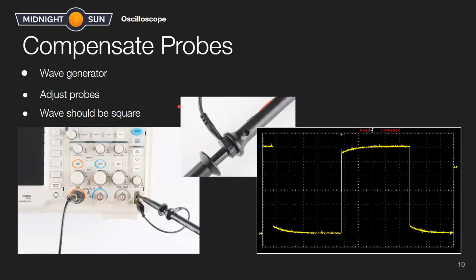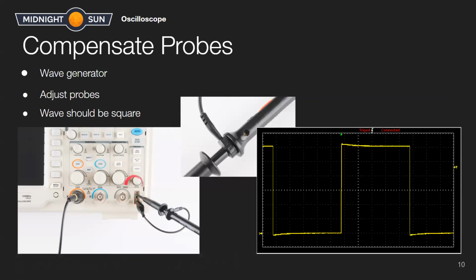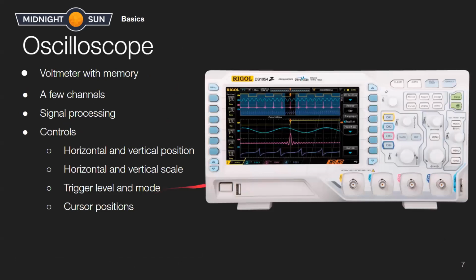Okay, so the way to compensate a probe is that all oscilloscopes will have some sort of waveform generator, and this is usually set to a 1 kilohertz square wave. In this case, it's on the bottom right. This isn't the exact model of oscilloscope that we would have in our bay, but it's similar on ours. So it's still on the bottom right corner, and there's two, it's difficult to see because it's pointing towards the camera, but there's two metal terminals here. You would connect the probe like this, and then it's connected to channel 1.